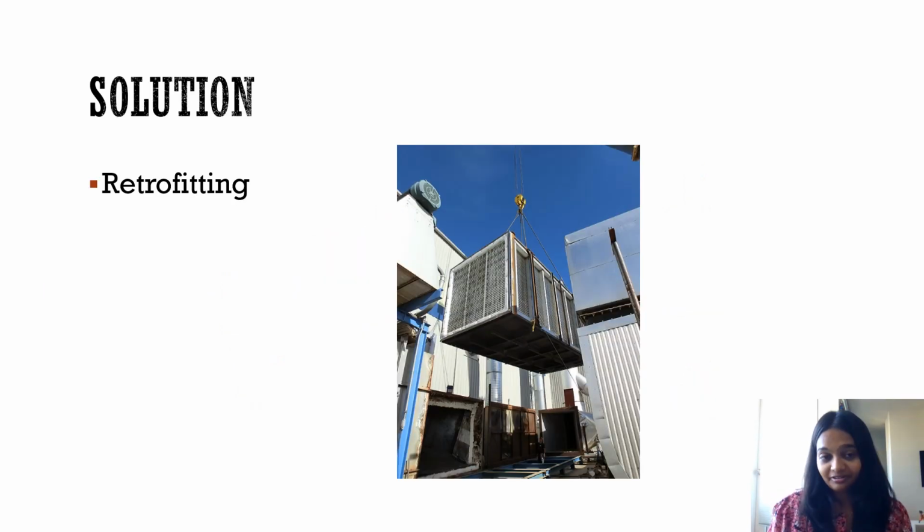Now, how to solve it? It could be by retrofitting. If the baffles are not properly placed, you can place the proper baffle, or if it's a design issue, you can replace or change that particular part.